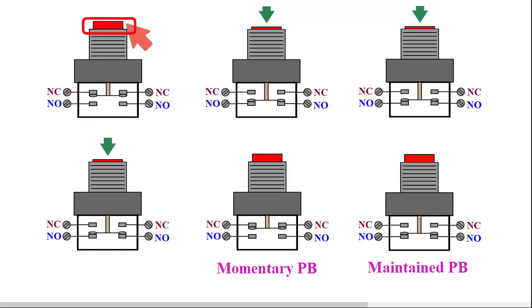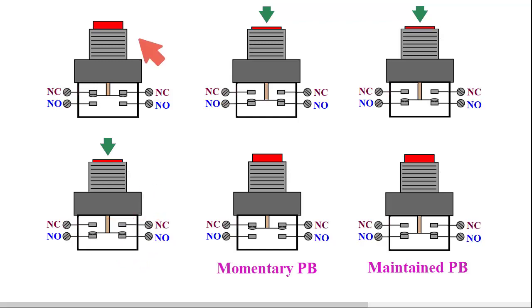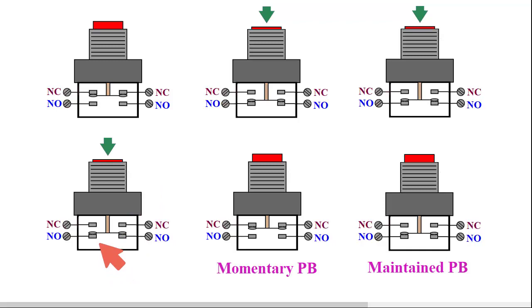There is a place where pressure is applied. When pressure is given, the contact shifts to the lower position — the normally open contact becomes closed. When the push button is not pressed, the NC contact gives a logic 1 signal to the PLC and the NO contact gives a logic 0 signal. When it is pressed, the operation reverses: NC gives logic 0 and NO gives logic 1.